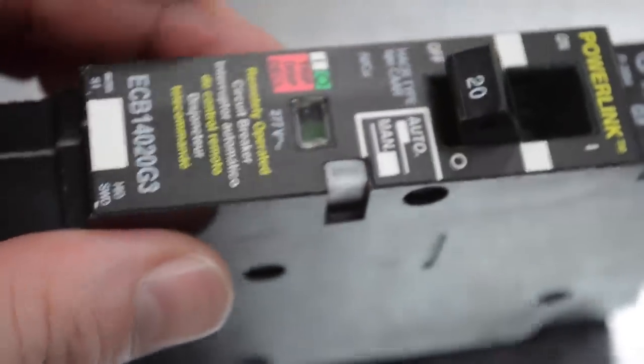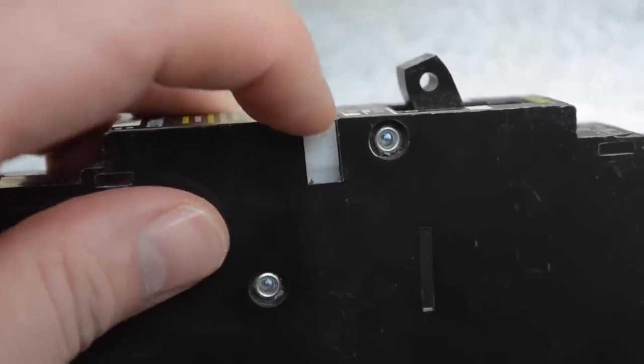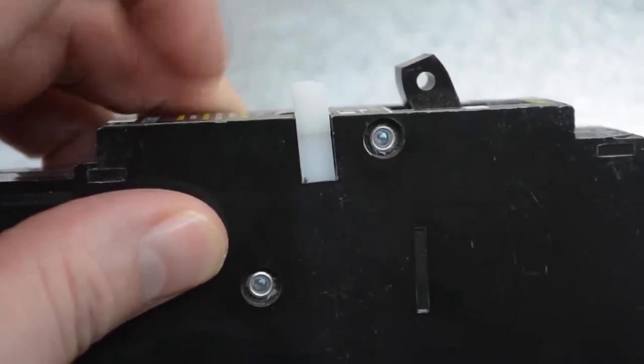Another good thing to test is all of these smart breakers have a little push button on them that is a disconnect switch. That little dip switch, if you look closely, says auto and manual. What that is in auto, that means that the controller and the network has control over that breaker. So it allows the normal function, the scheduling, everything to work to control that breaker. But when you click it into manual mode, it takes the Ethernet and the controllability away from anybody remotely. So it would essentially operate like a regular breaker when it's in manual mode.